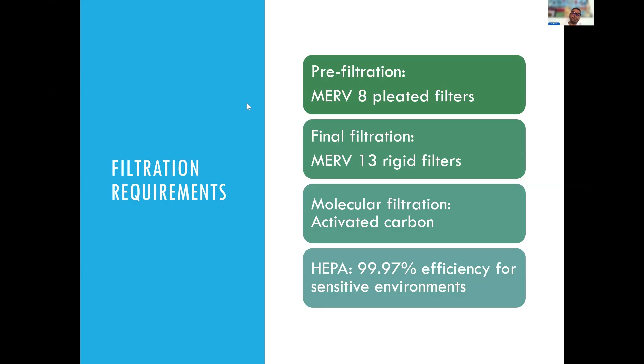These types of equipment will come in all different shapes and forms. So you may have an air handler where the manufacturer only suggested putting in a single MERV 13 pleated filter. Okay, so be it. Changing that to a MERV 8, you should consider the high flow rate that equipment is carrying. Some of these units can be 20, 30, 40 tons and pushing 50,000 CFM. Putting the incorrect type of filter in this application could very well cause that filter to buckle. So you want to make sure the product you're putting in there can withstand whatever the CFM requirements are.